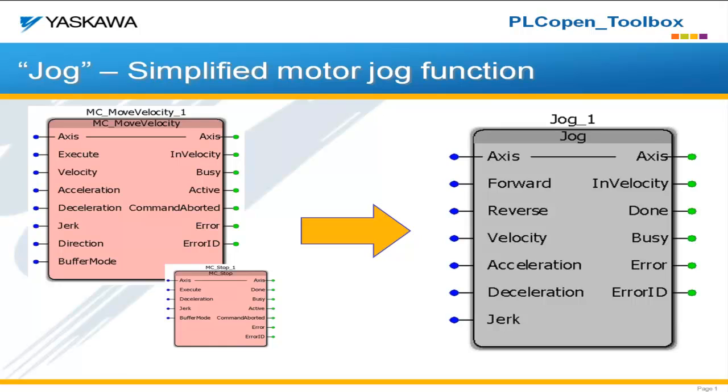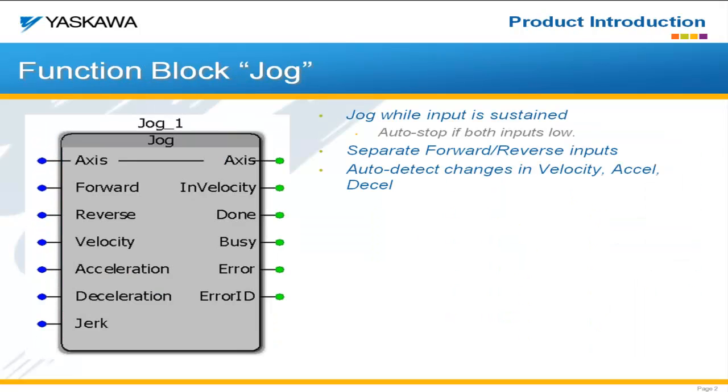We've done all that logic for you and put it into a single function block called the jog function block. With the jog function block, and we'll see it in operation in just a second, we have two separate inputs, one to command forward motion and one to command reverse motion. As long as those inputs are high, it will continue to do the motion.